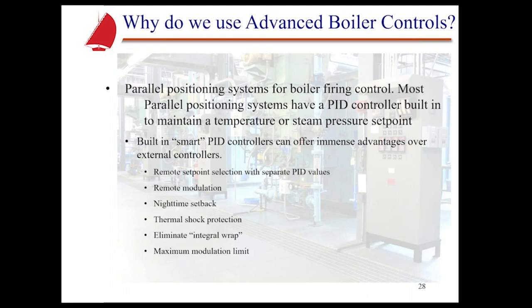And a huge advantage is maximum modulation limit. During some times, for instance, of maybe a year, you may want to limit that particular boiler or application to say 50% modulation. I had an application where the particular end user had bought twice the boiler that he actually needed, because in the next 5 years to 8 years, they were actually going to increase the size of their plant and they were going to need more steam. But they were ramping up to 100% firing rate, coming straight on down and shutting down. So they were cycling constantly. And by being able to dial in a maximum modulation limit, we are able to limit that down to about 30 to 40%, and therefore greatly reduce the amount of cycling. And that's something that you can do with a system like this.